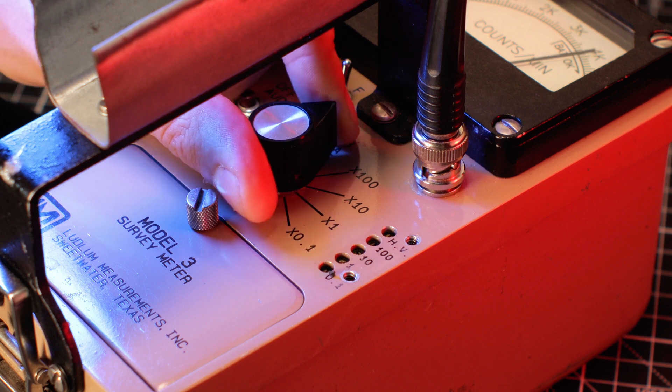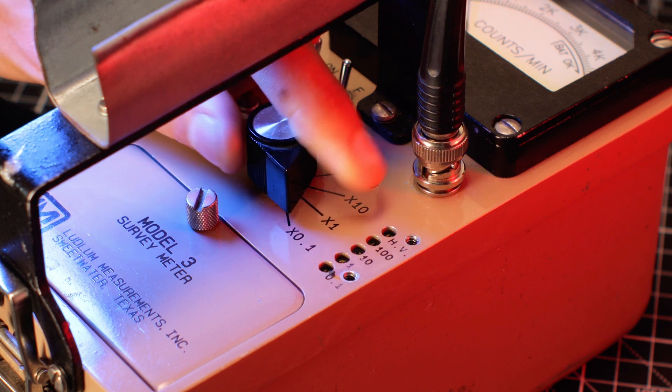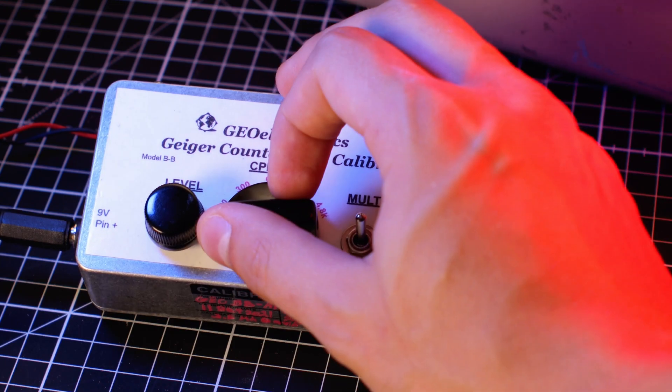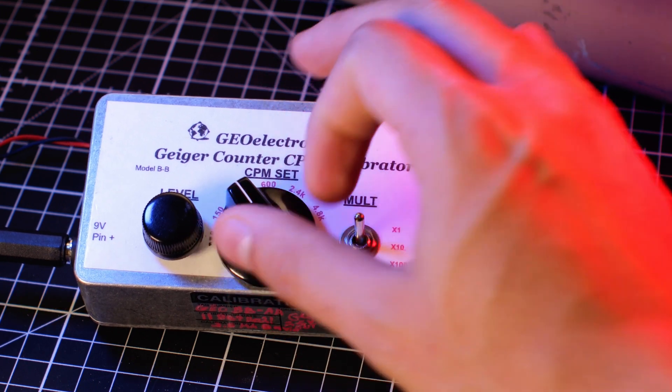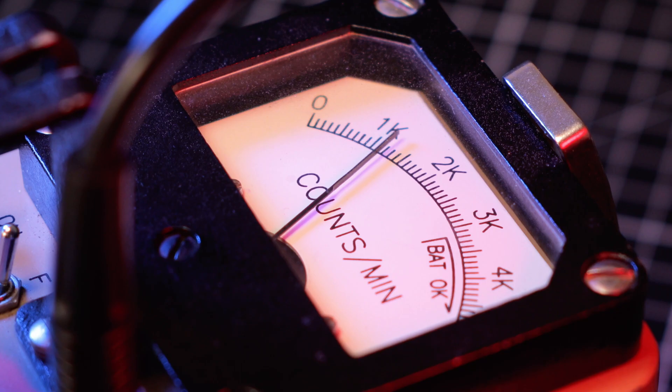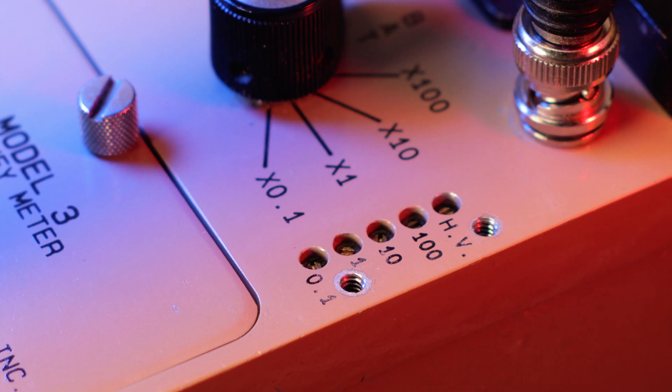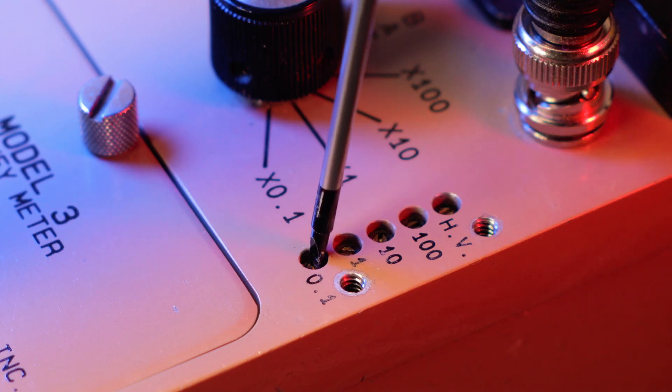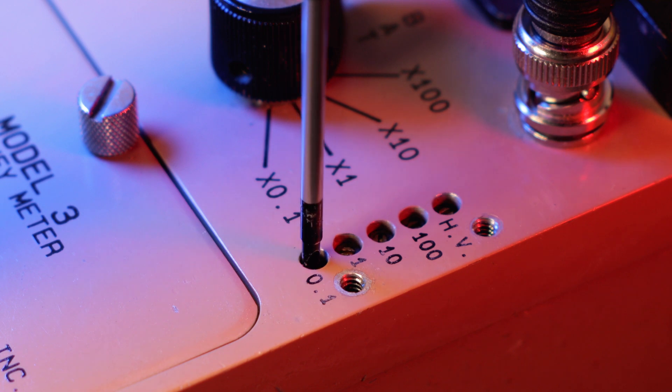Now simply turn on your Geiger counter and set your pulser to generate a desired amount of clicks. Make sure the needle on the meter is showing the correct amount of CPM generated by the pulser on every scale. If it's not, then adjust the calibration potentiometers until it is right where you want it.